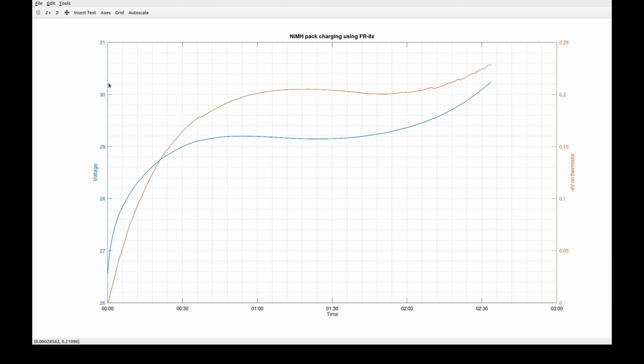However, in this case I introduced that current shunt, and this is the voltage on the battery side, so on the charger side it should be higher by about 120 millivolts. So I would think that the actual voltage on the charger side should be around here, 30.4 or something like that.